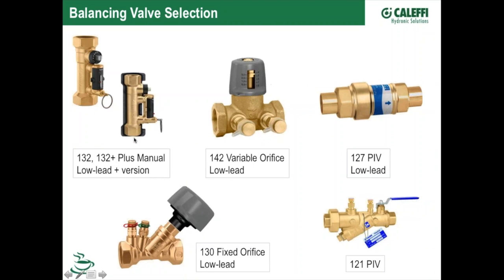so you can balance domestic water recirc loops by temperature. This is a variable orifice valve, also a low lead version, because that can sometimes be used in domestic water applications. Here's a 130. This is a fixed orifice valve, with PT ports on these valves, so you can put a differential pressure gauge on that and adjust or confirm the settings. These are auto flow valves here. This has a little cartridge or spool in there that moves back and forth based on the pressure change in the system. This is another version of that valve there. This one here, you can get the cartridge out and remove it.